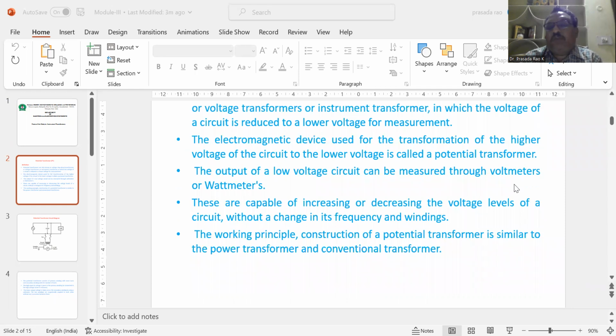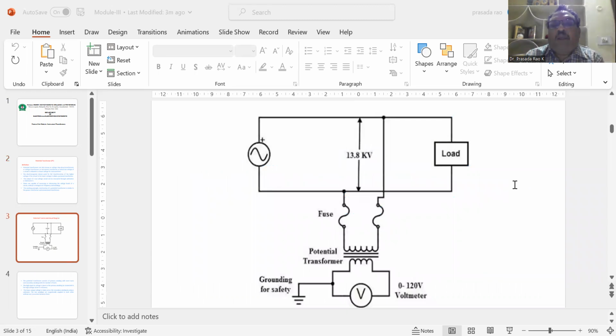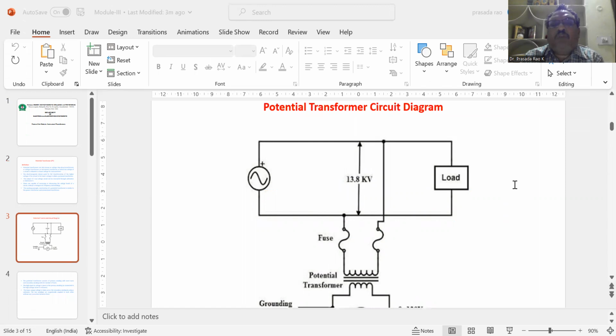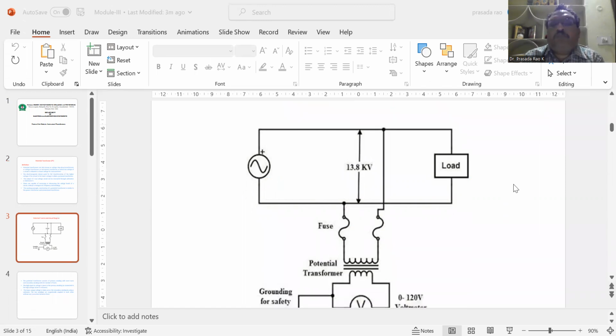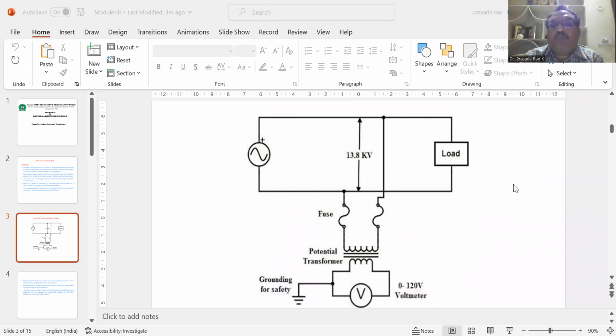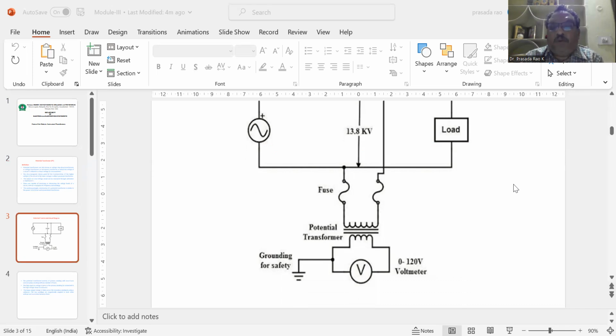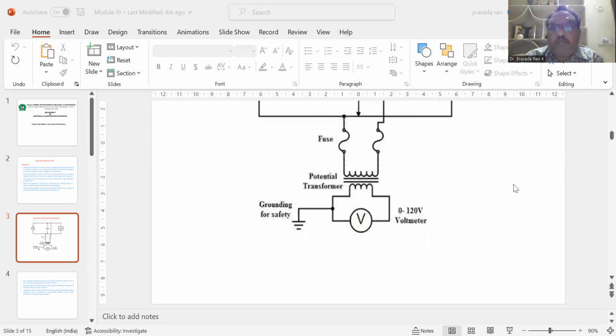The construction and working principle of a potential transformer is similar to the conventional power transformer, and this is the circuit diagram for the potential transformer for the measurement of high voltages. Here the high input voltage to be measured is applied across the primary of the transformer. This high voltage, nearly 13.8 kilovolts, is applied across the primary, and this voltage is stepped down to a very low voltage approximately equal to 0 to 120 volts, and this reduced voltage across the secondary is measured by using the voltmeter.